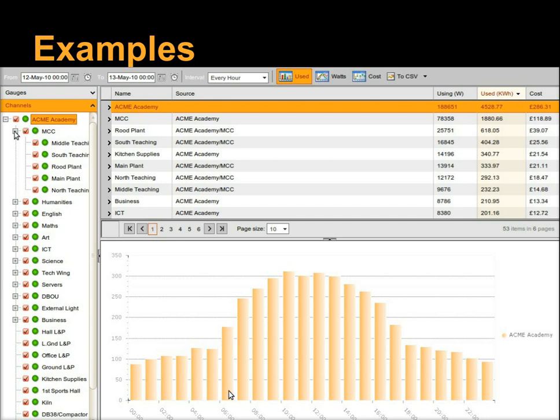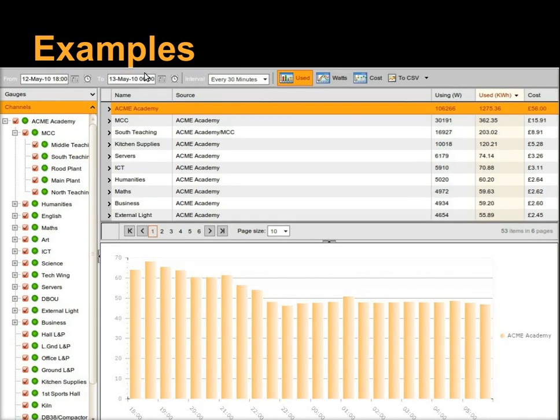No one's in the school before 6, and no one is in the school after 1800. This is just a school. It's not a multi-purpose facility. And so when no one's there, a third of the energy is being used. And if you move the time from 1800 to 6 the next day at 600, you get this. You get the 1200 kilowatt hours being used when no one's in the school.